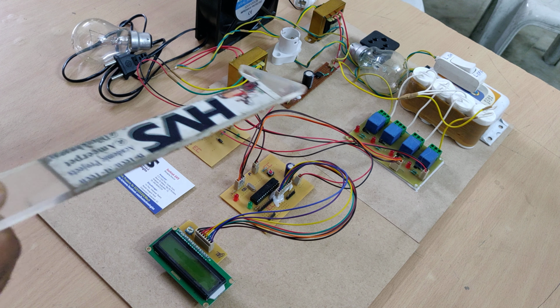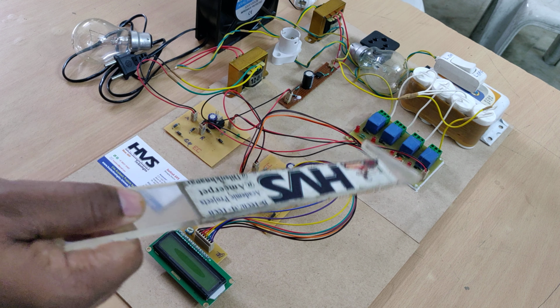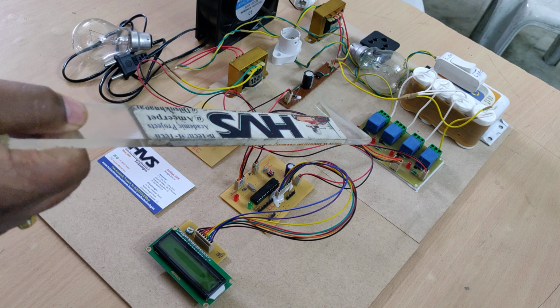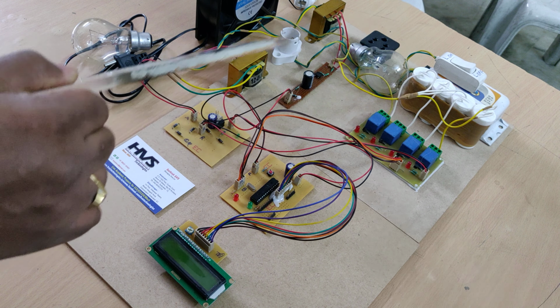Generally, for power factor correction purposes, only one capacitor is needed. The microcontroller independently checks the power factor value. If it is below 0.9, ideally it should be near 1, but that's not possible since we don't get a pure resistive load. That's why we monitor around 0.9 to 0.91. Whenever it is below that, the microcontroller decides to control the relay board by adding these capacitors to eliminate the harmonics while performing power factor correction.